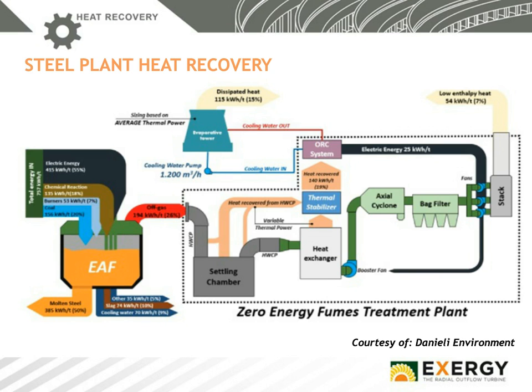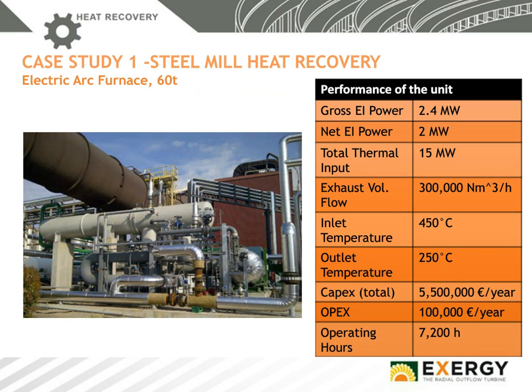The second way is to use the existing cooling system for the flue gas line, because in every electric arc furnace you have a cooling system for the flue gas line, and it usually operates at about 90 to 100 degrees, usually not more than 120 degrees. Obviously, the efficiency of the heat recovery system will be lower, but as an opposite effect, the cost of the system implementation is much lower, because there is a very, very small intervention on the flue gas line. So getting back to this case, we have flue gas which is quite hot.